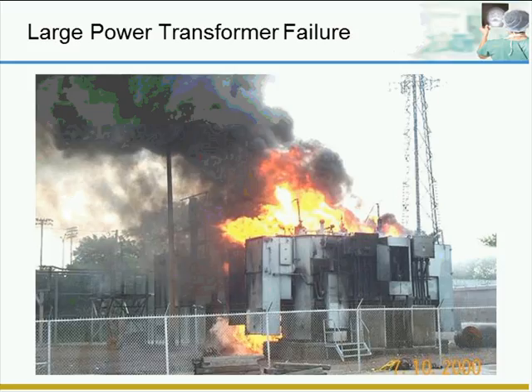Another thing everybody should be aware of is PCBs. If you have a PCB-filled transformer, that is hazardous material and requires special handling. If there's ever a leak or a fire such as this, OSHA and a lot of regulatory commissions will be involved. Business continuity planning. Make sure you check your voltages. If you have a spare transformer or have specialized voltages, it may lead to longer lead times, so just know your equipment.